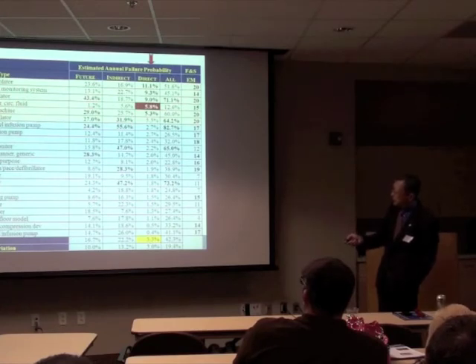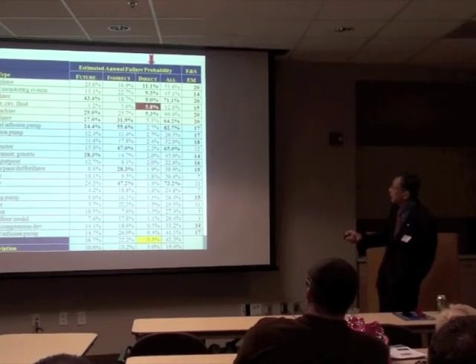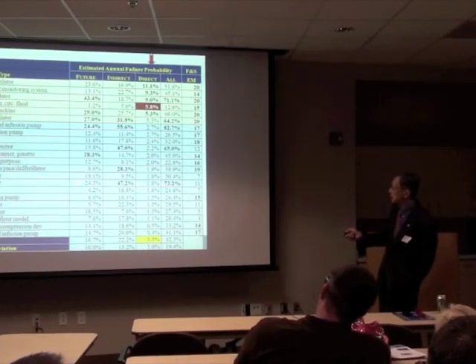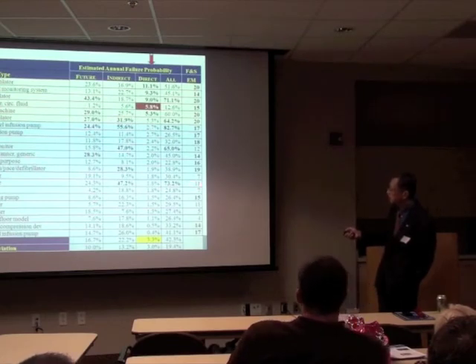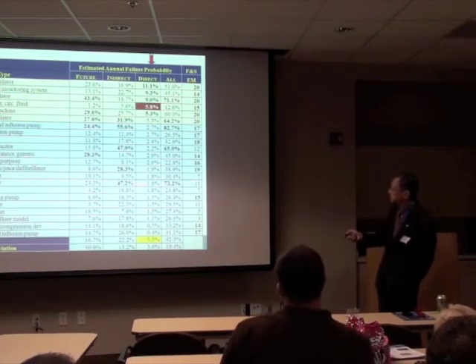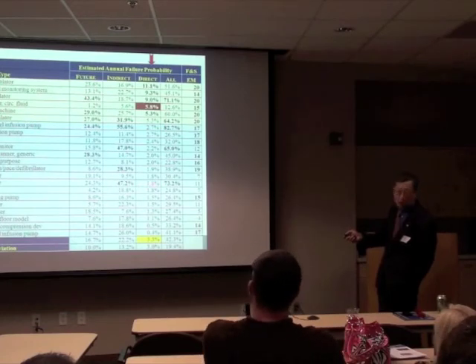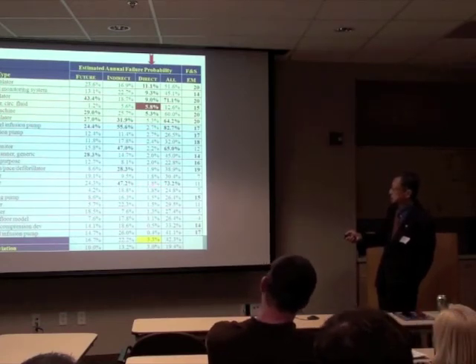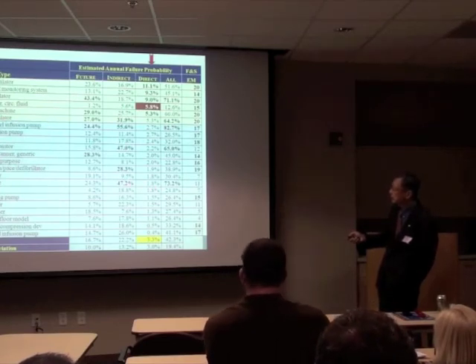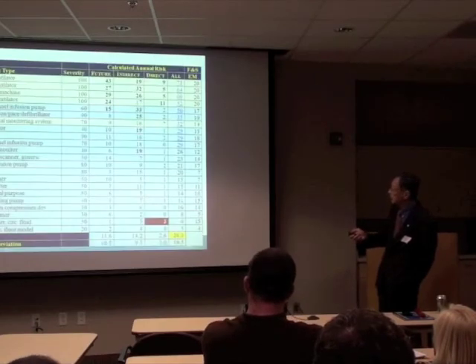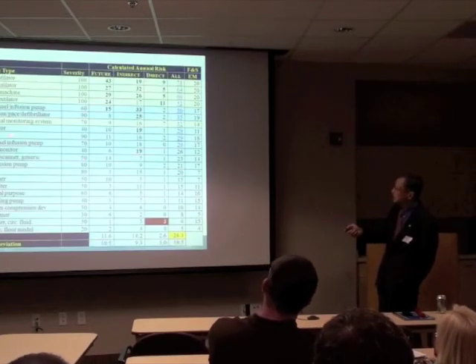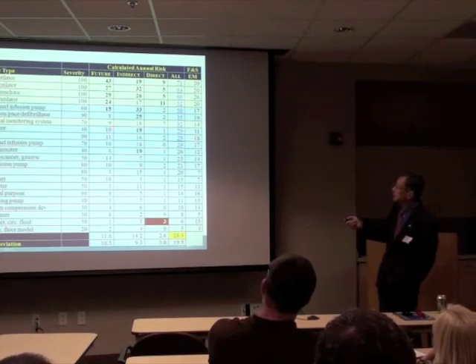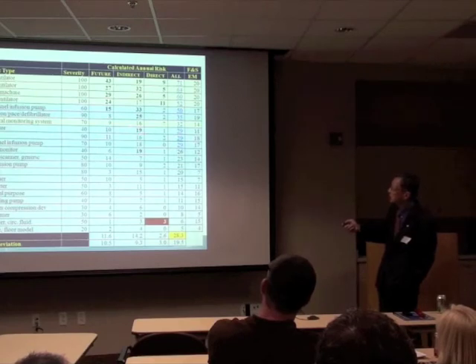I put an arrow here - an NIBP monitor is a low-risk device, and error probability in the technical model wouldn't even be included. The probability of failure on the direct side is typically less than 2%. But there's quite a bit of problems from the user side. When you put this together, all of a sudden NIBP became fairly high in overall risk because of the indirect factor.